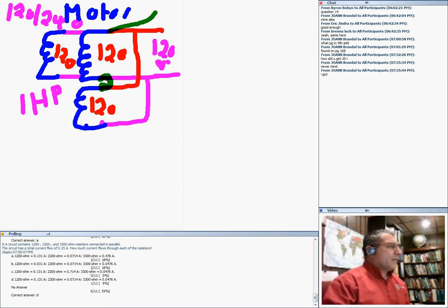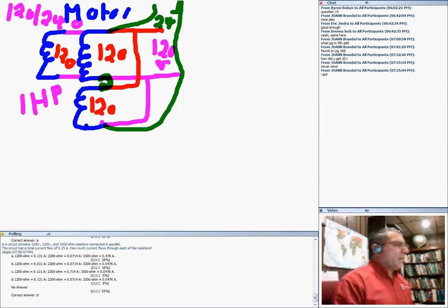These two ends tied together, can you see that? And the voltage from here and the voltage from here - now right here is my 240. Look at the green connection: you take two parts of the coil, wire them together, and the other side you bring to the 240. Now my motor is running at 240 and still a 1 horsepower motor.